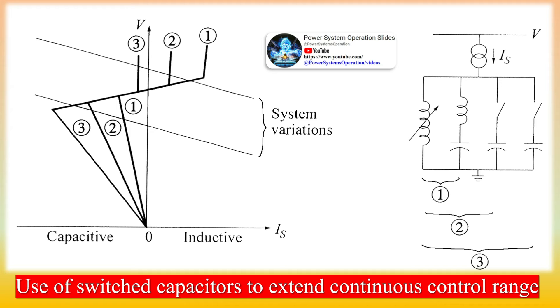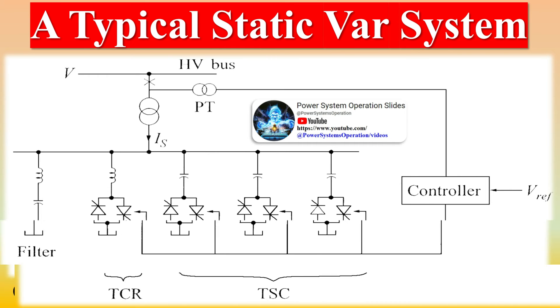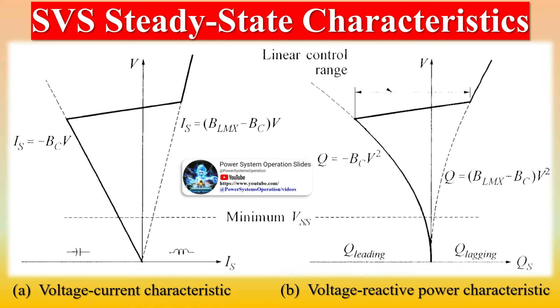The technical advantages of STATCOM over SVC are primarily: faster response, requires less space as bulky passive components such as reactors are eliminated, inherently modular and relocatable, it can be interfaced with real power sources such as battery, fuel cell, or SMES (superconducting magnetic energy storage). A STATCOM has superior performance during low-voltage conditions as the reactive current can be maintained constant. In an SVC, the capacitive reactive current drops linearly with the voltage at the limit of capacitive susceptance. It is even possible to increase the reactive current in a STATCOM under transient conditions if the devices are rated for the transient overload.